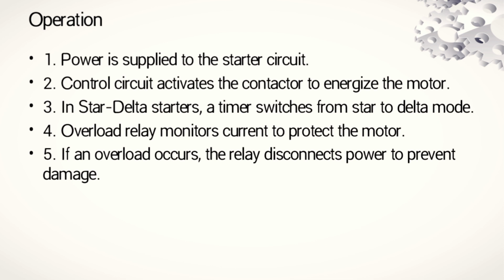The operation, how it works. First, power is supplied to the starter circuit. You can have an AC source or a DC source. Second, the control circuit activates the contactor to energize the motor. Third, in a star delta starter, a timer switches from the star to delta mode. Fourth, the overload relay monitors current to protect the motor. As we have said, the relay is like a circuit breaker. And fifth, if an overload occurs, the relay disconnects power to prevent damage. So the relay protects all the components of the system.